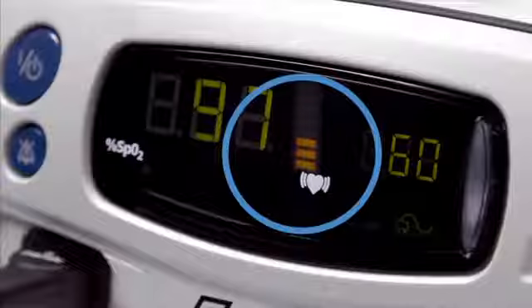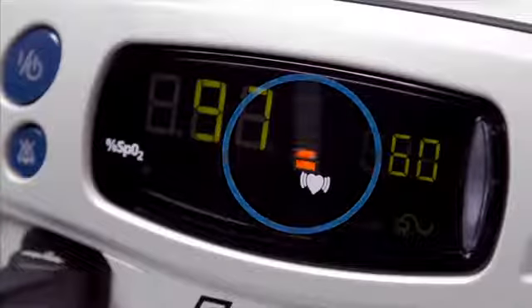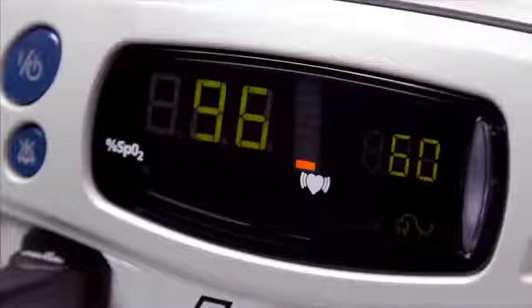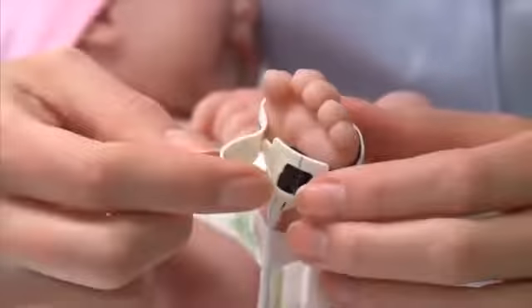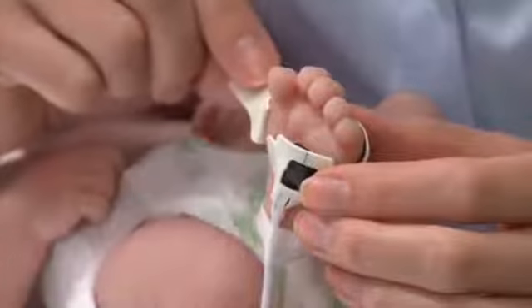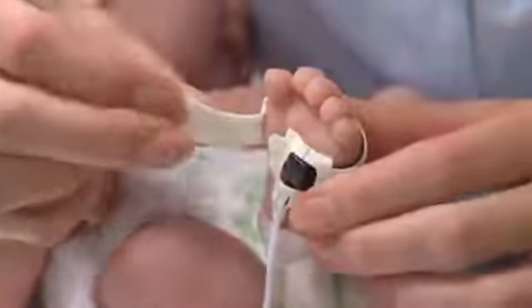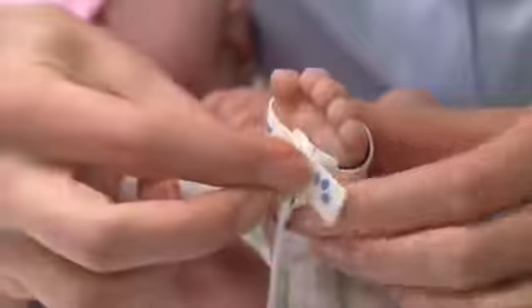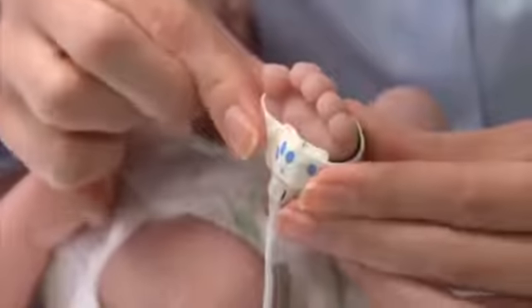Nonin pulse oximeters have a pulse signal quality display that measures the sensor signal. If the signal is low, the emitter and detector may not be in proper alignment. Reposition the sensor to see if a stronger signal can be obtained. If repositioning does not increase the signal quality, try a different site or check that the patient's foot is warm, relaxed, and well perfused.